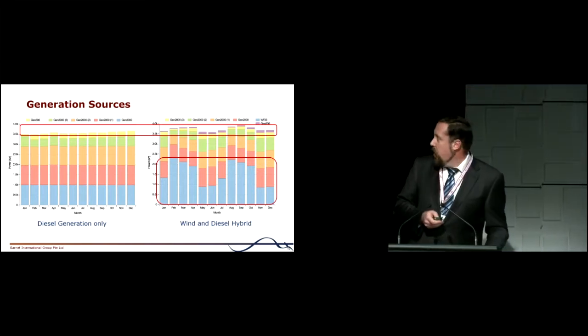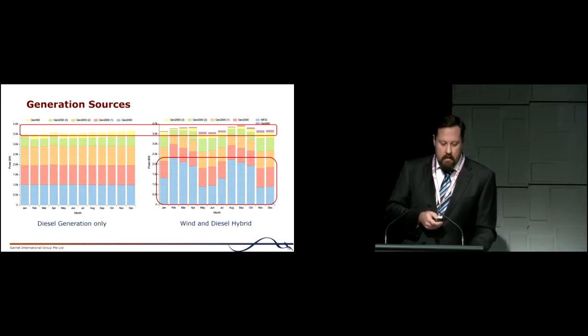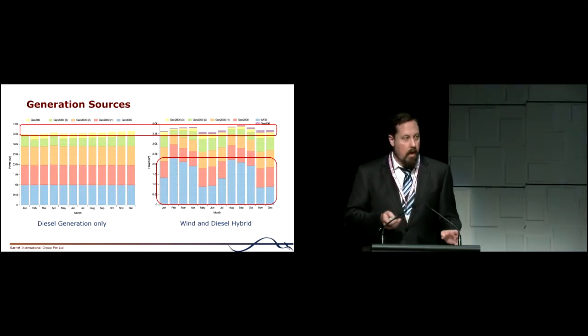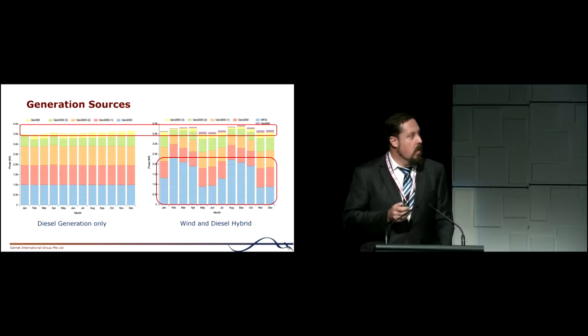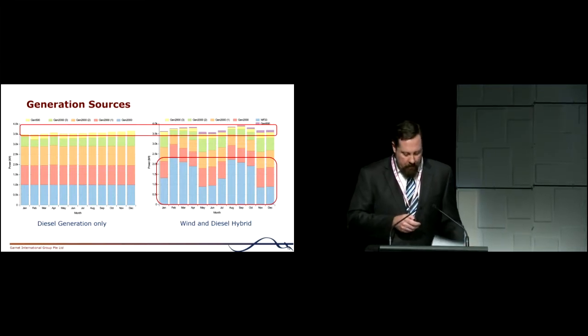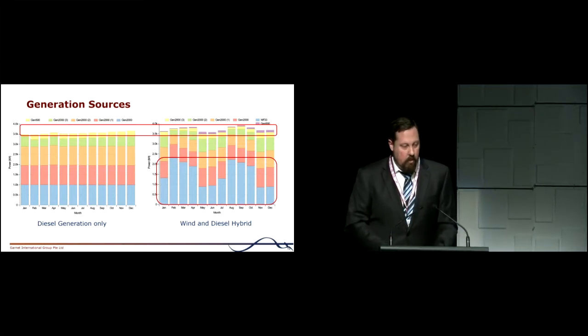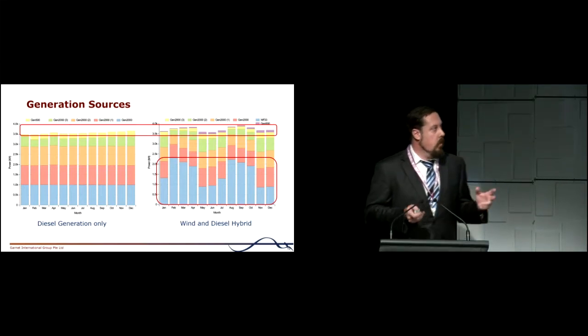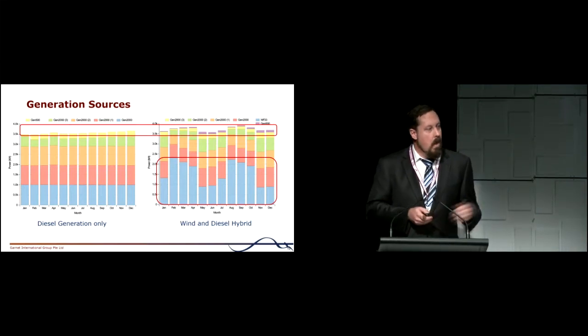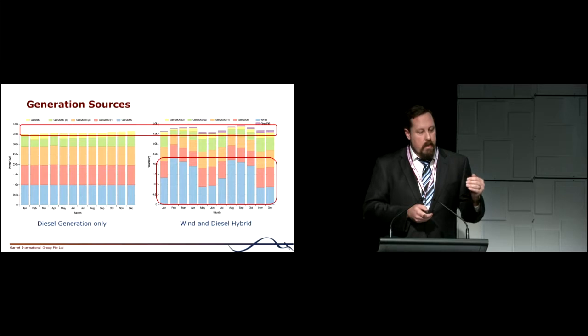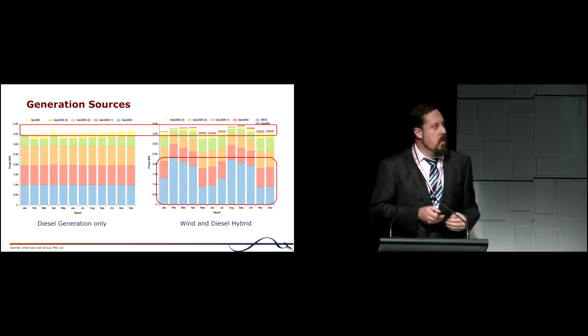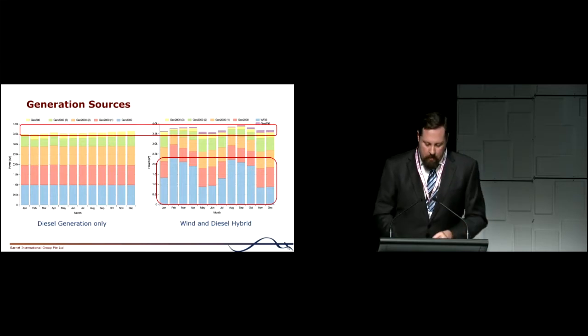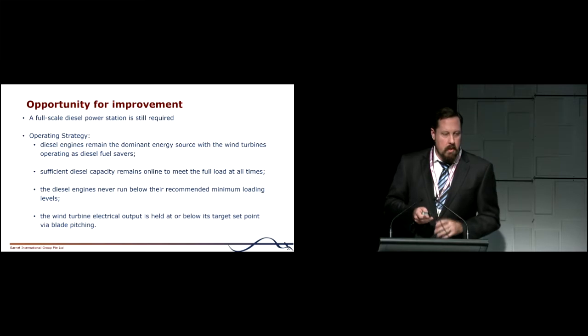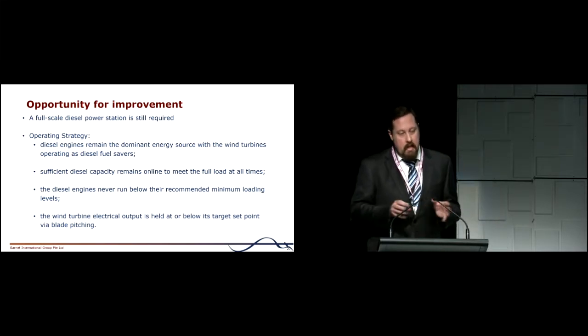So what's driving this? Inefficiencies in the generators running on idle, or having a spinning reserve at capacity when the wind farm is operating. This has driven us to look beyond the wind diesel hybrid, at what else we can do to reduce that idling load and diesel consumption for generators that aren't efficiently loaded. They're basically spinning reserve in case there's a dip in the wind. So there's an opportunity for improvement that we see at the moment.